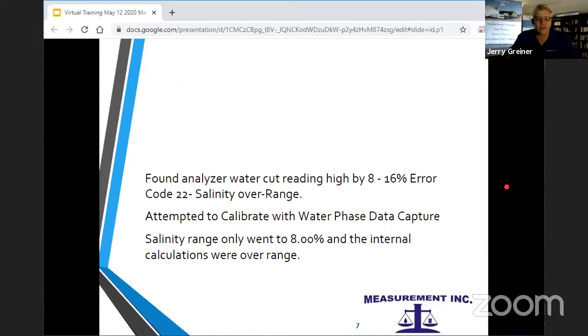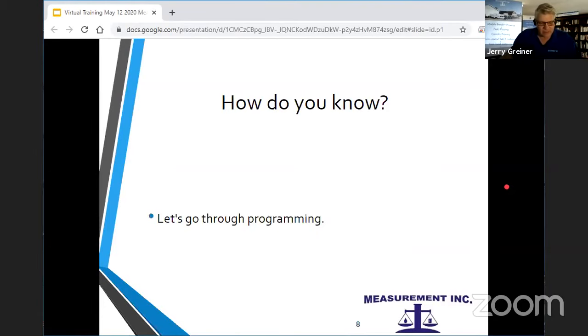There was a code in it. If you went through the codes, it said salinity overrange, a code 22. And so we attempted to calibrate this. The way you calibrate it, I'm not going to go into that right now, but you use a water phase data capture. And when you do that, normally that captures it, it fixes it. But there is still a calculation overrange.